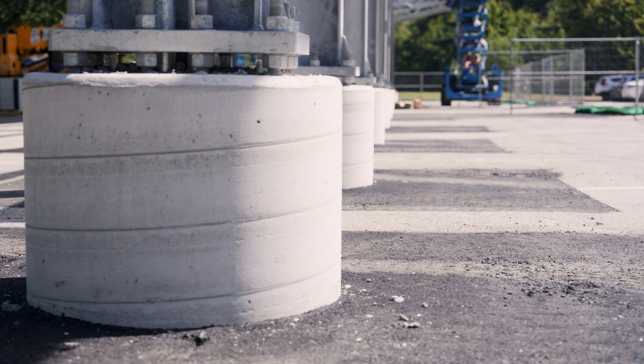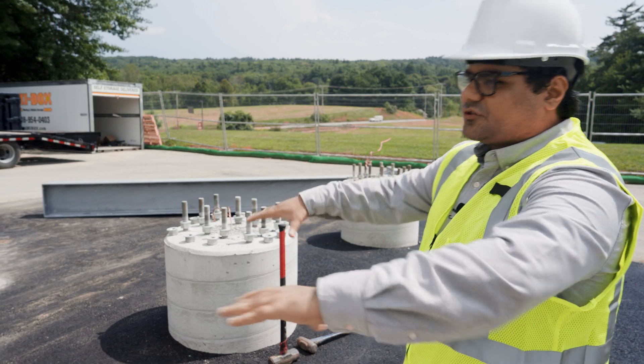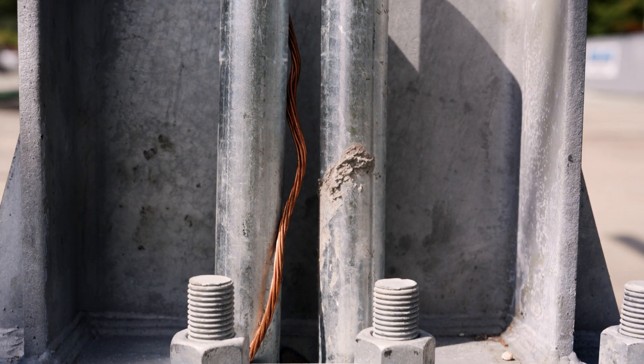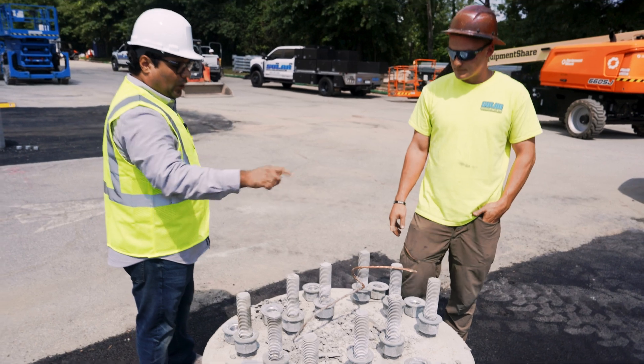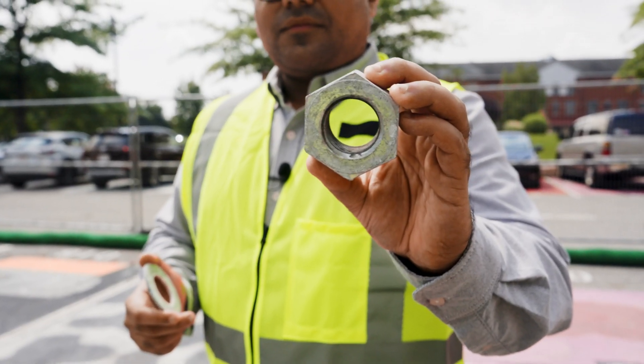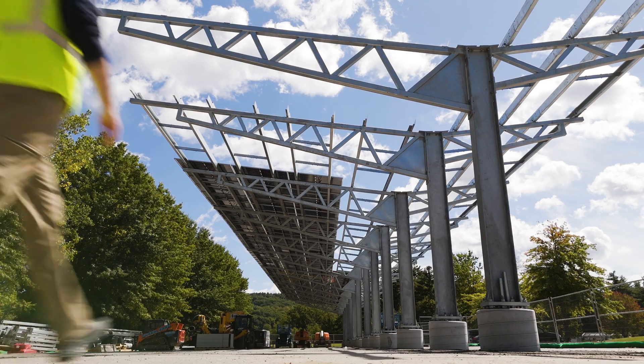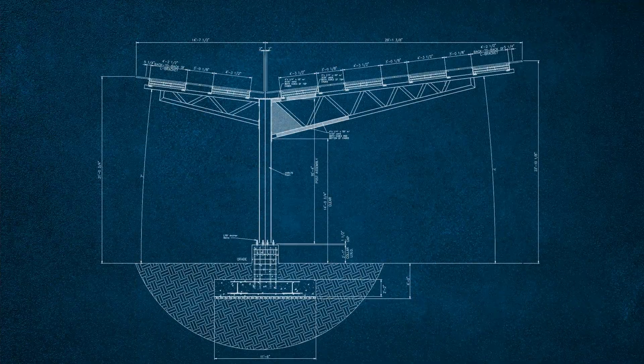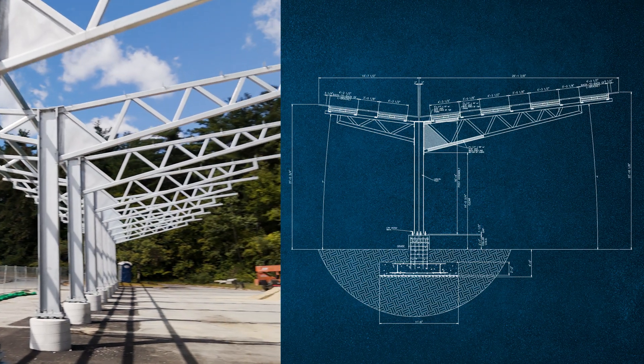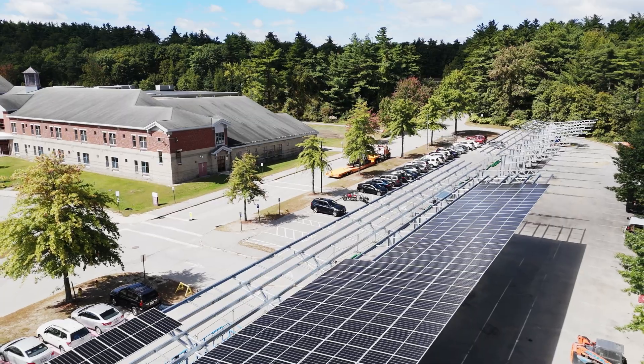What we're looking at here is the base of the canopy. There's a rebar kit that goes into the ground and there's concrete that's poured around it. There's a ground wire that basically grounds for any lightning strikes — if you touch the canopy itself you're never going to be electrocuted. There are 10 screws that all get bolted on, and then you've got steel purlins on which the modules are mounted. This is a standard Y-frame with a two-to-five degree tilt on the canopy that helps with water management and also tilts the canopies towards the south, where the most optimal exposure to the sun is.